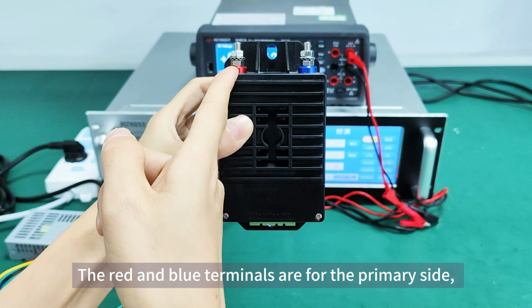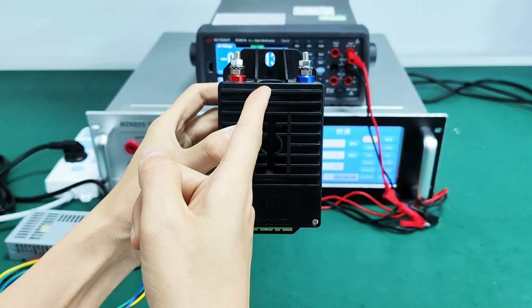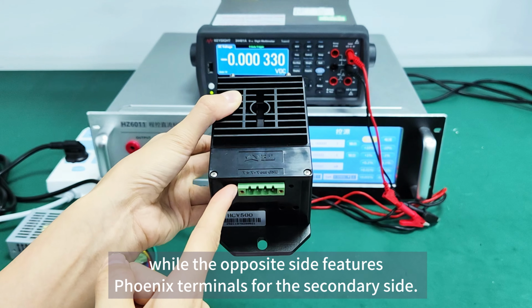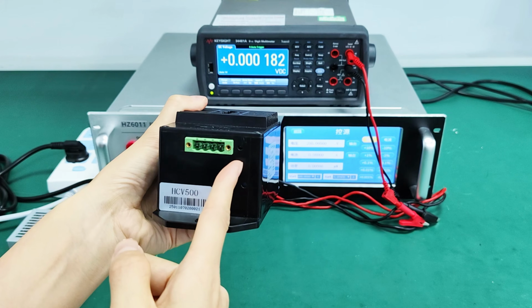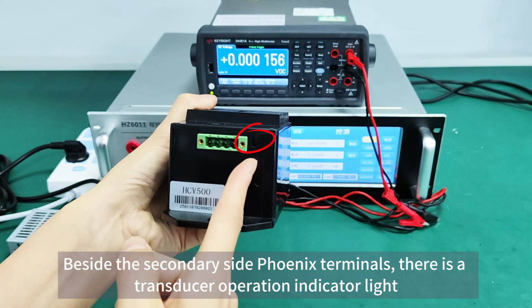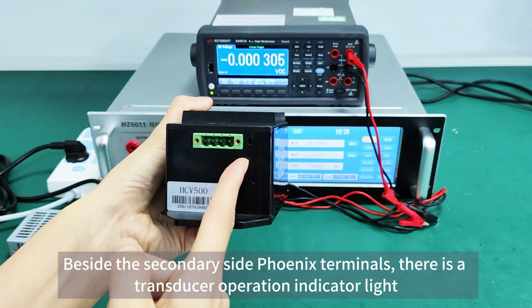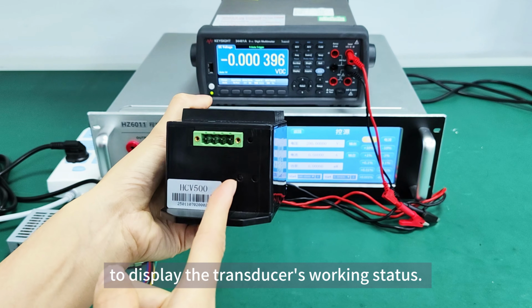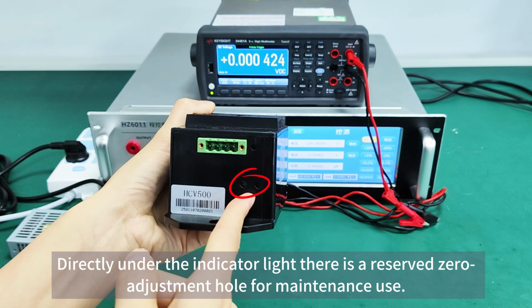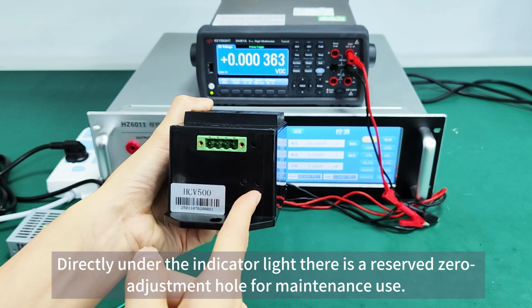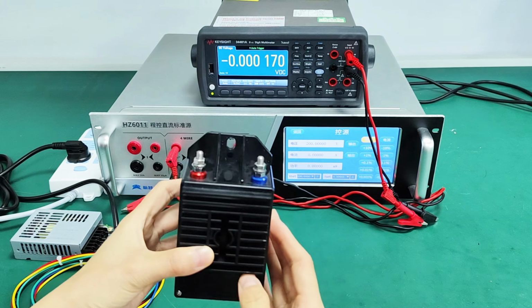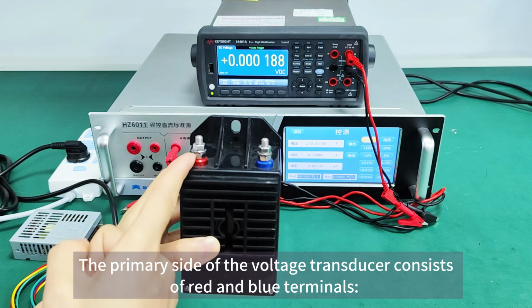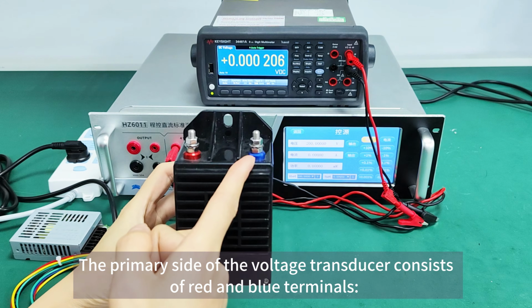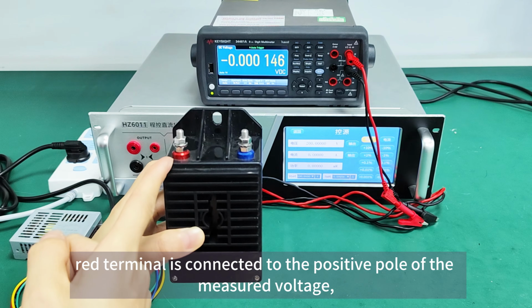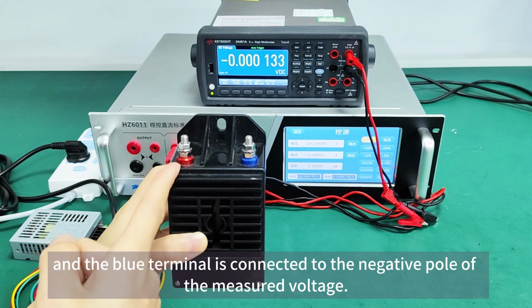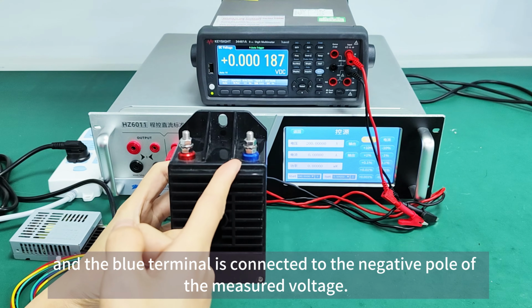The red and blue terminals are for the primary side, while the opposite side features Phoenix terminals for the secondary side. Beside the secondary side Phoenix terminals, there is a transducer operation indicator light to display the transducer's working status. Directly under the indicator light there is a reserved zero adjustment hole for maintenance use. The primary side of the voltage transducer consists of red and blue terminals. Red terminal is connected to the positive pole of the measured voltage, and the blue terminal is connected to the negative pole of the measured voltage.